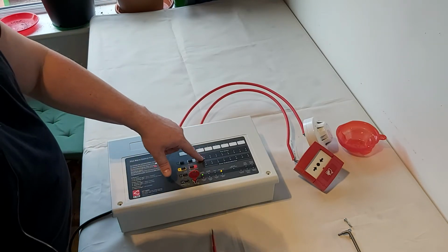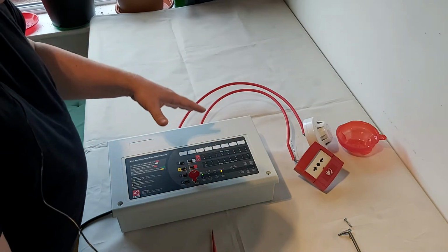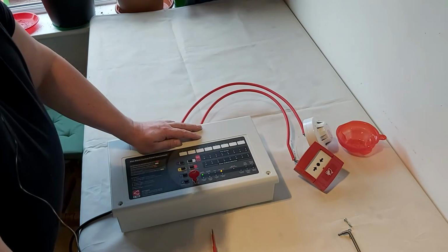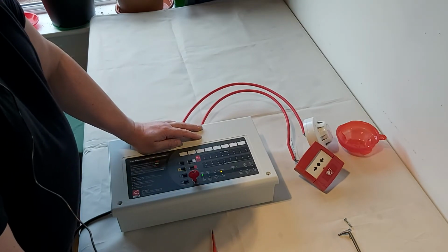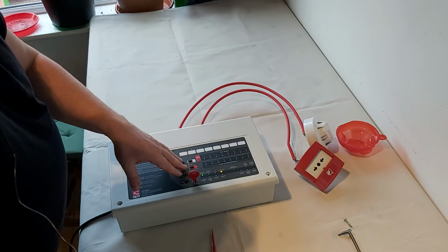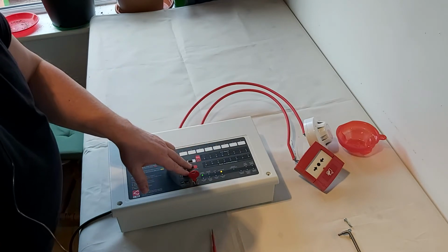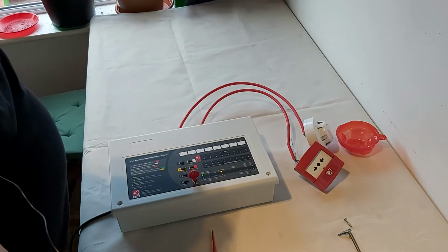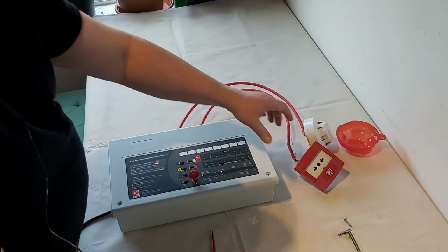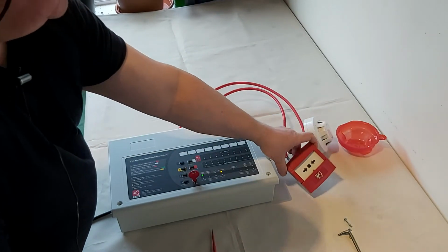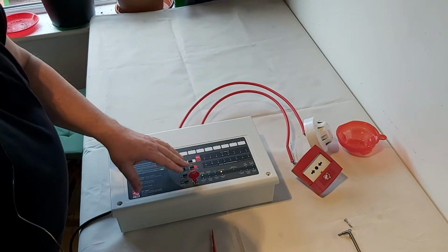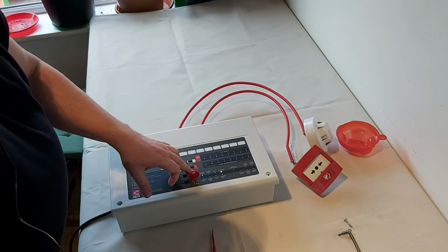When the alarm goes off, main fire alarm, one thing you do usually is silence the sounders. Obviously you don't want to silence the sounders when it's the real fire, but there's no fire and you're just investigating, so you can silence the sounders by pressing that button. And then let's say somebody accidentally pressed one of those, so you then go to that and restore the setting on this, and then you can use reset button.